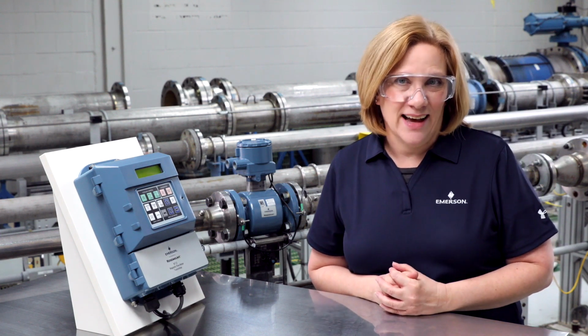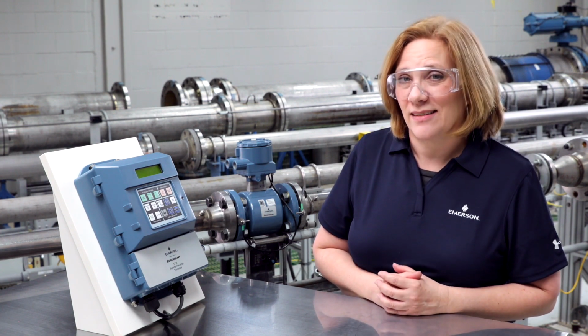If you are running the coils at 5 Hz, then the diagnostic will look at the 5 Hz signal-to-noise ratio and look at the 37 Hz signal-to-noise ratio if you are running at 37 Hz. If the signal-to-noise ratio remains below 25 for 1 minute, the high process noise alert message will display on the screen. The coated electrode detection diagnostic provides a means of monitoring insulating coating buildup on the electrodes. Buildup over time on the electrodes can compromise the flow measurement.